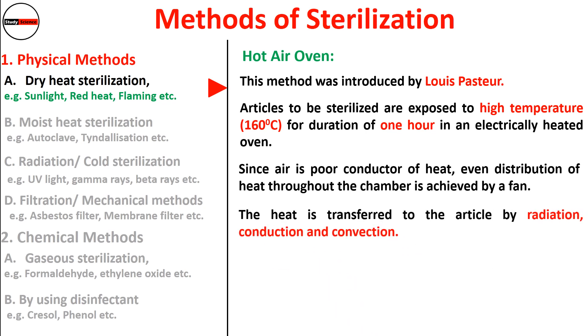The next dry heat method is the hot air oven, widely used in laboratories for sterilization of glassware, metals, etc. This method was introduced by Louis Pasteur. Articles are exposed to 160°C for one hour in an electrically heated oven. Since air is a poor conductor of heat, even distribution is achieved by a fan. Heat is transferred to the article by radiation, conduction, and convection.